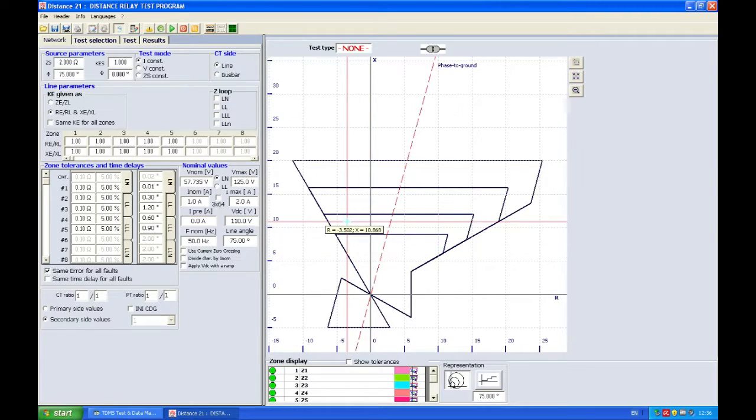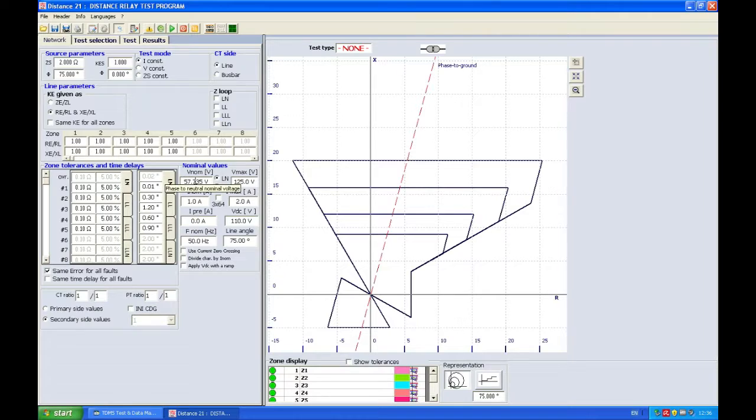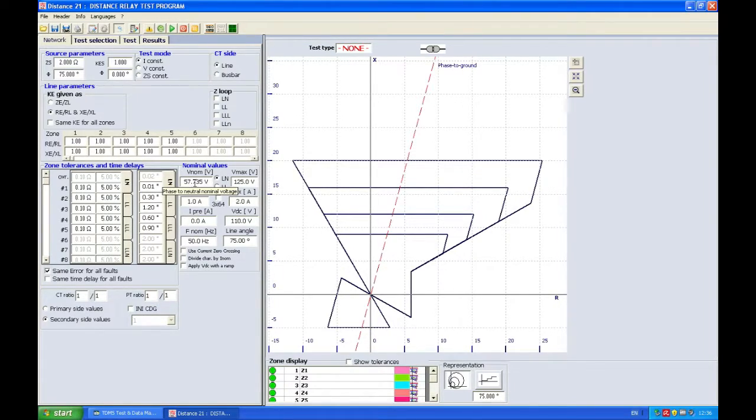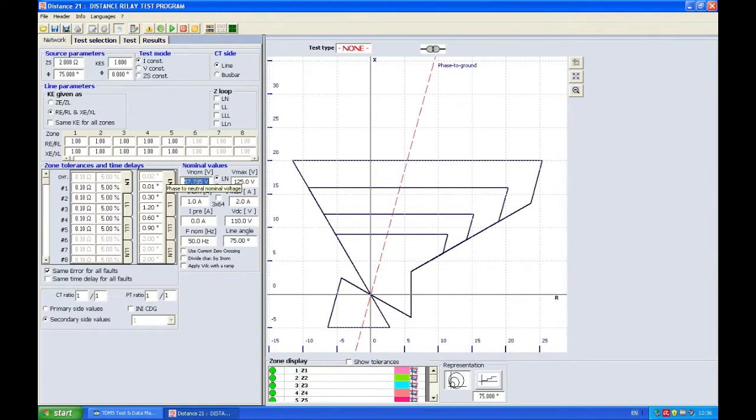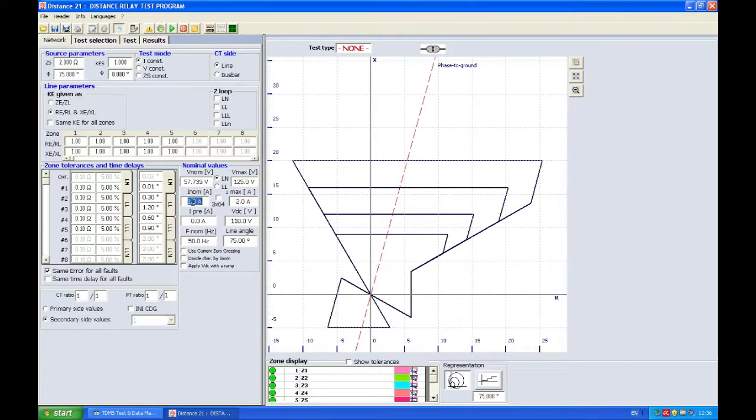We can just take a look here and see if all the values which we imported from the relay file are OK. Usually you don't have to do that but I'm checking that my nominal voltage is 57.735 volts phase to ground which is 100 volts phase to phase. 1 amp is the nominal current for my relay because it has the ratio of 300 to 1 CT.